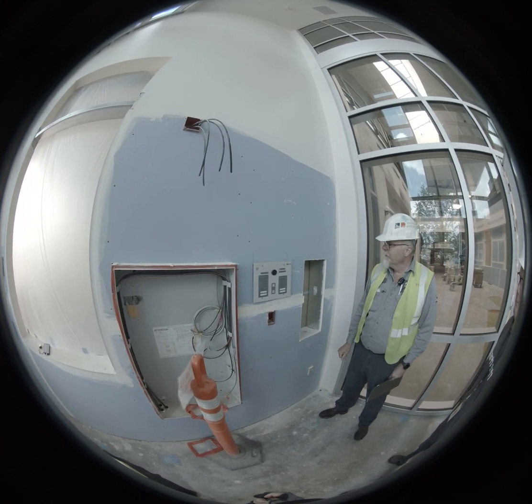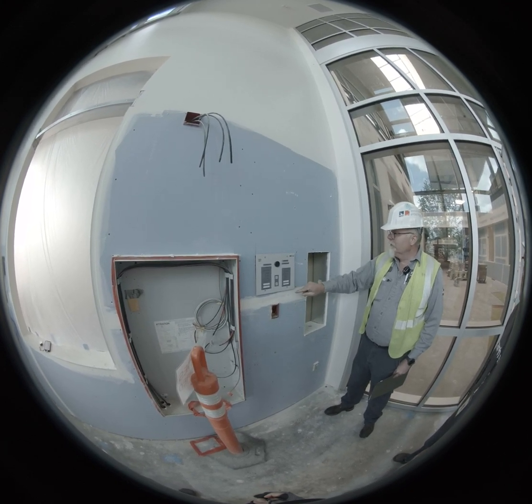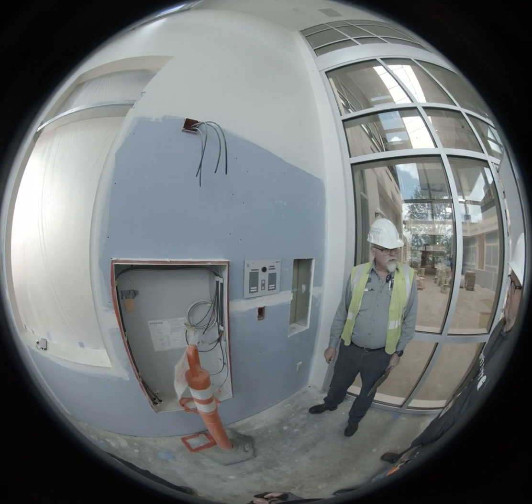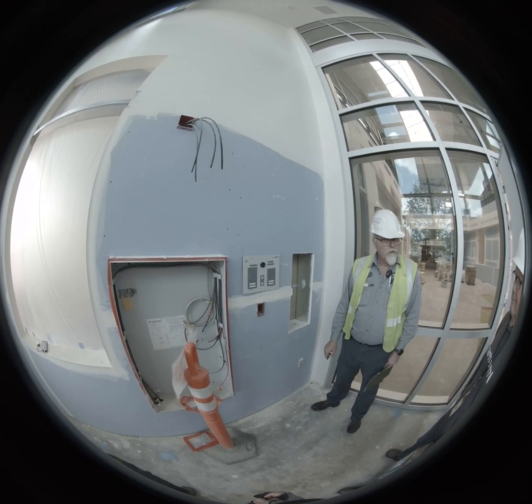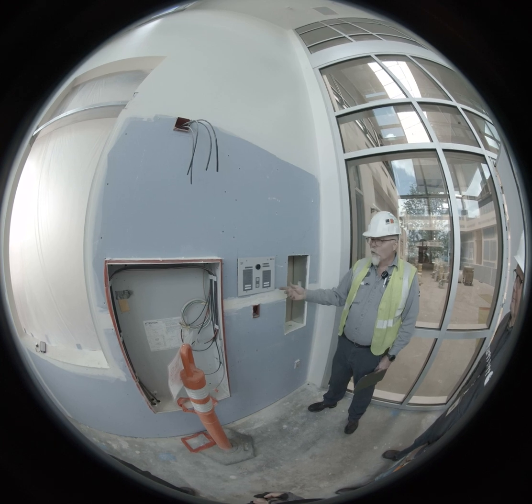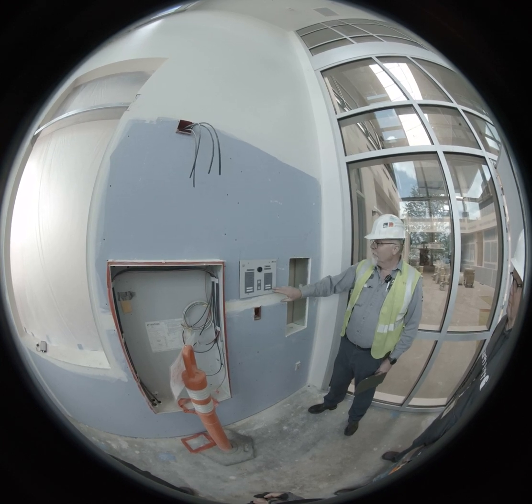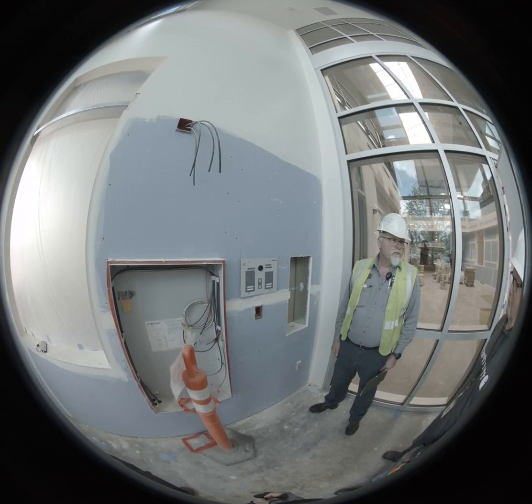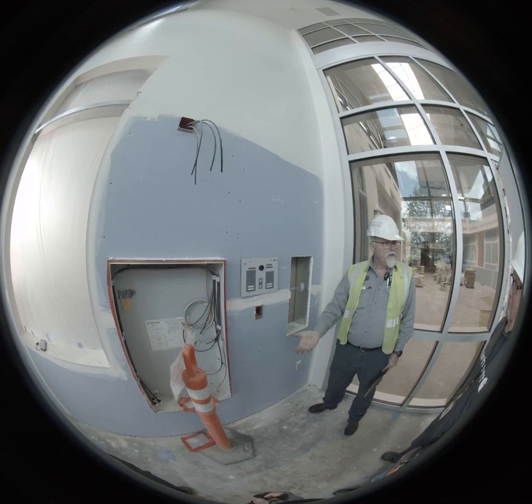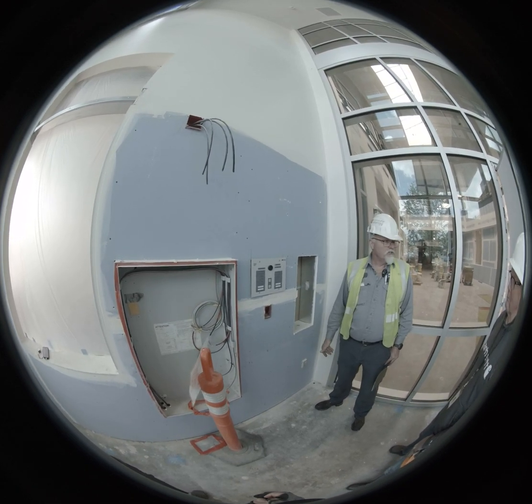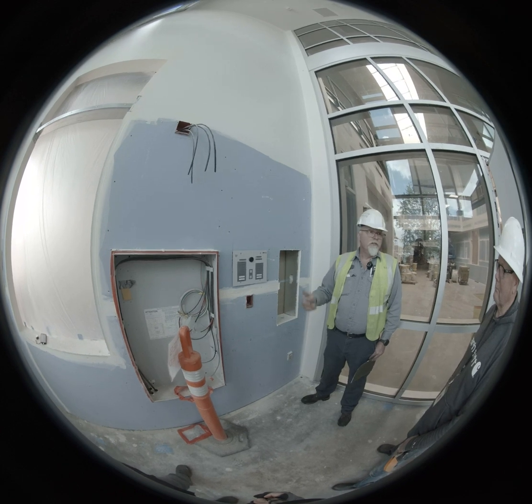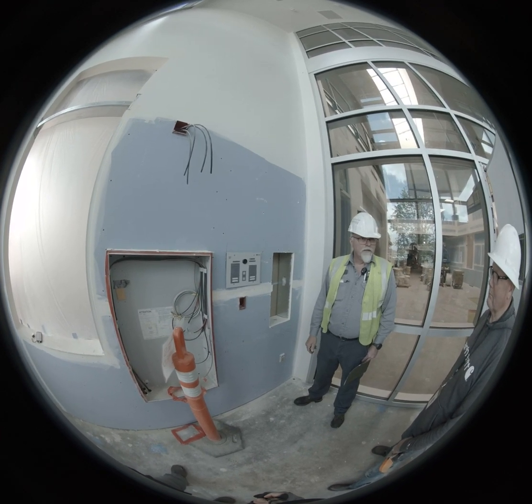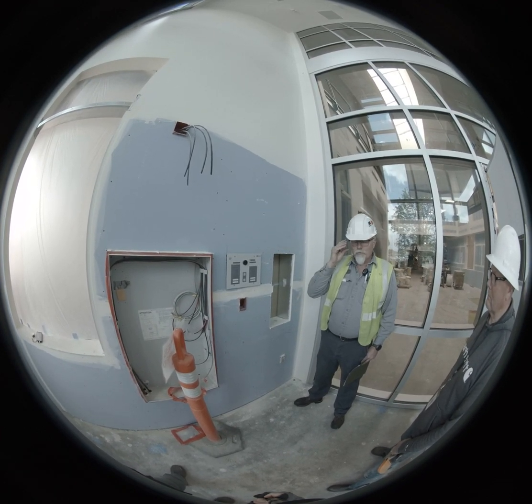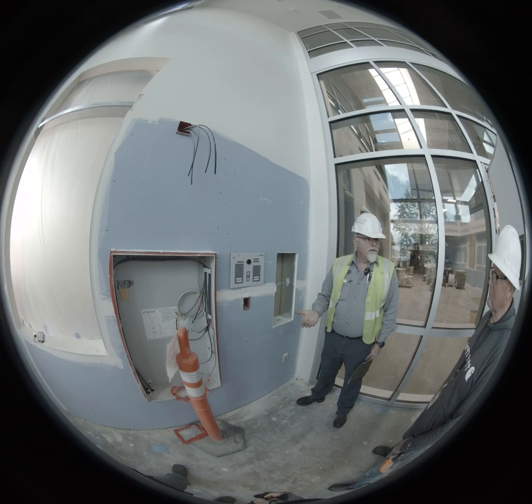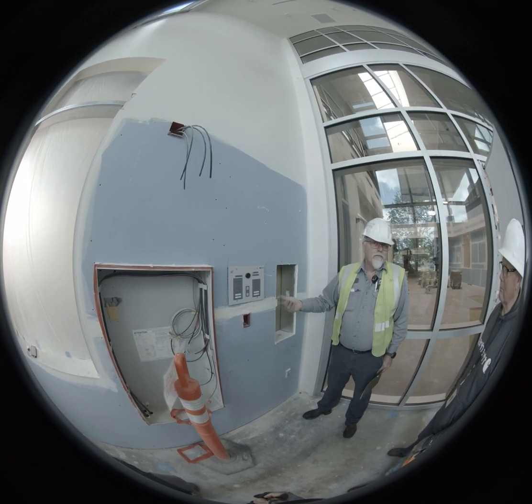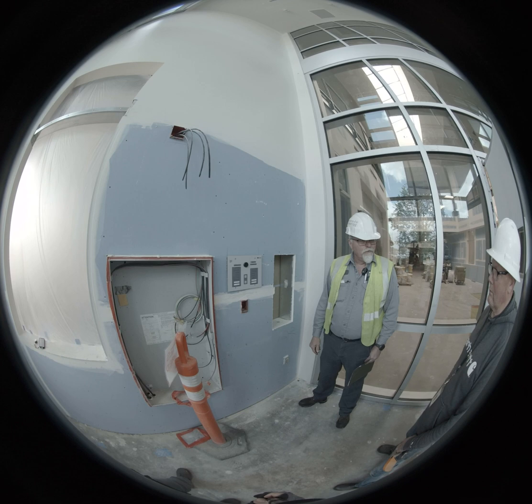Yep. Battery over voltage and battery charge failure are both out of the charger itself. So if you turn the battery charger off, or even if you get an outage, you're going to see a battery charge failure, because during the outage the battery charger does not have power until the gen comes back up. Every once in a while people will want us to throw a timer in there so that doesn't come on, but it's a good audible to tell you.